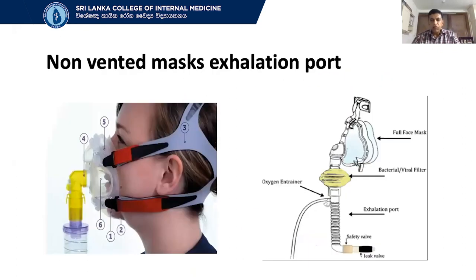Now, this is one thing that we could do for a single limb: we can use a non-vented mask, and you have an exhalation port distal to the filter. You see at the bottom of the tubing you have the exhale port, so exhalation only happens from the bottom, but only after the air goes up through the filter. This is one modification that we can do. If you compare with the picture on your left, you can see that if you don't do that, the air leaks out to the environment quite easily. Now, these makeshift, transformed units are not fully sealed, and there is a theoretical possibility that the virus can disseminate from these places.